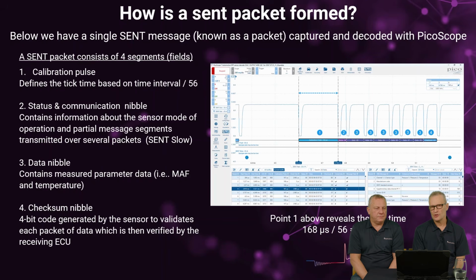Whilst we're not converting it into the correct units, so you're not getting numbers in degrees centigrade for example, what we do get is a decimal value that rises and falls as temperature increases. It's not a precise diagnosis, but it qualifies that the sensor is doing something and outputting something.